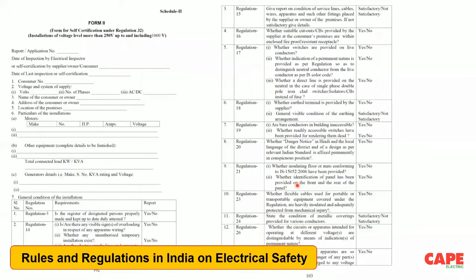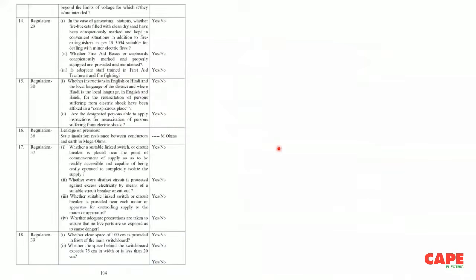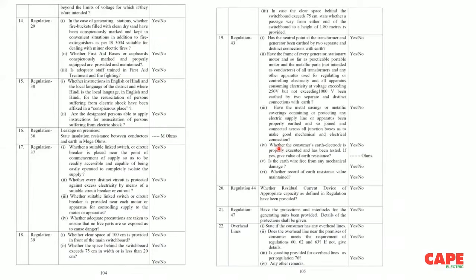Please note that this format, which is Form 2 in the upcoming regulation, is actually about compliance to the regulation. For example, in a consumer premise, you see regulations 15, 16, 17, 18. This format is asking about compliance to the regulation. And in my view, if you do compliance as per this particular format, of course, electrical safety on a large scale cannot be achieved. In a residential case, it's okay, but in a large building it will be very difficult to achieve electrical safety. In an industrial or a large commercial installation, it is very difficult.